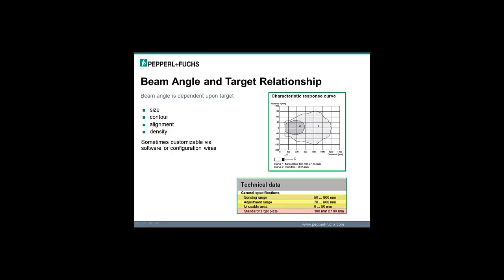Okay, here's a screen capture of a characteristic response curve that's found in any ultrasonic sensor's datasheet. And you can see that the beam angle is going to be dependent upon the target. So you've got curve number 1, or area coverage number 1, and area coverage number 2. Number 1 is a 100 millimeter by 100 millimeter flat plate, so a very 4-inch square wide plate. This curve 2 is in response to a 25 millimeter or a 1-inch diameter rod or round bar.